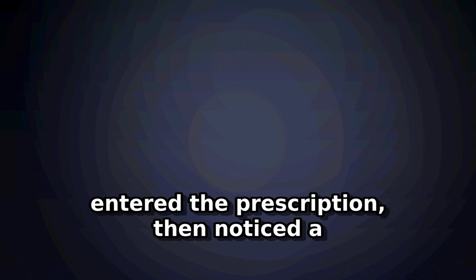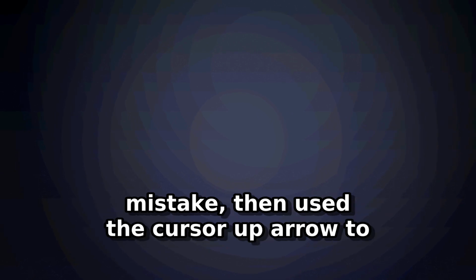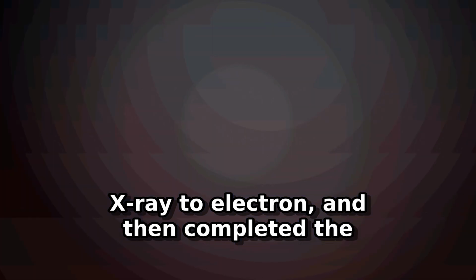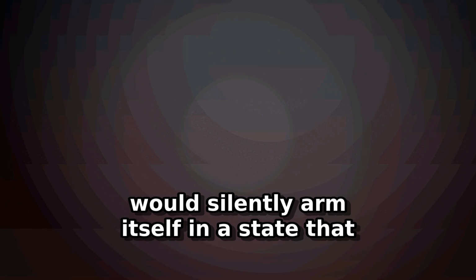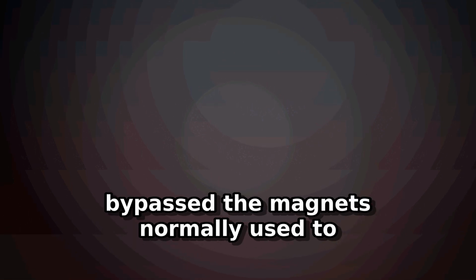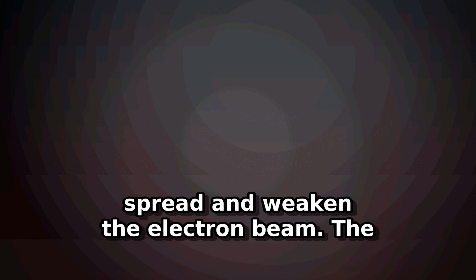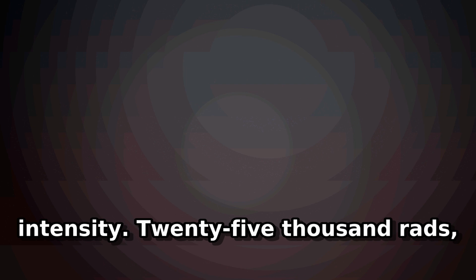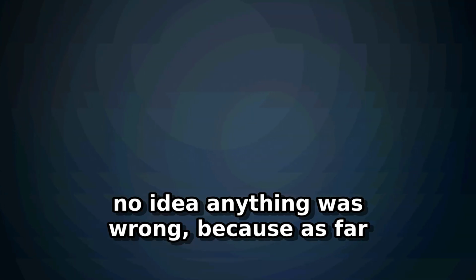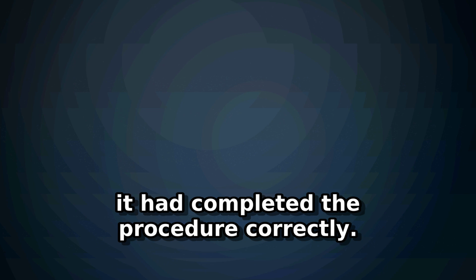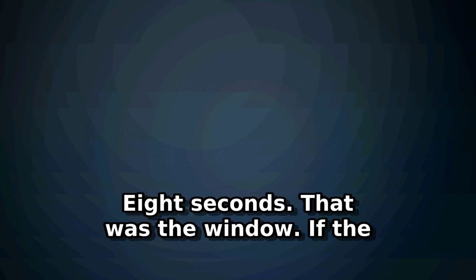After hours of trying, Hager found the pattern. If the operator entered the prescription, then noticed a mistake, then used the cursor up arrow to go back and change the beam mode from X-ray to electron, and then completed the edit within 8 seconds, the machine would silently arm itself in a state that bypassed the magnets normally used to spread and weaken the electron beam. The beam would fire at full, undiluted intensity, 25,000 rads focused down to a point. The machine had no idea anything was wrong, because as far as the software's internal counter knew, it had completed the procedure correctly. 8 seconds.